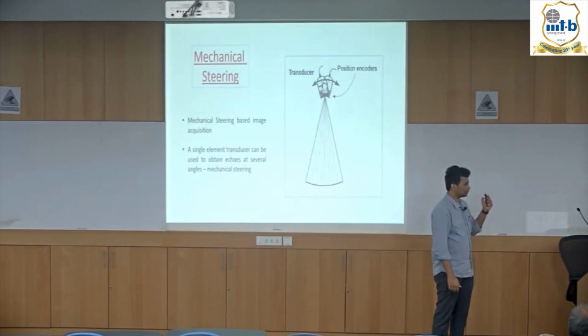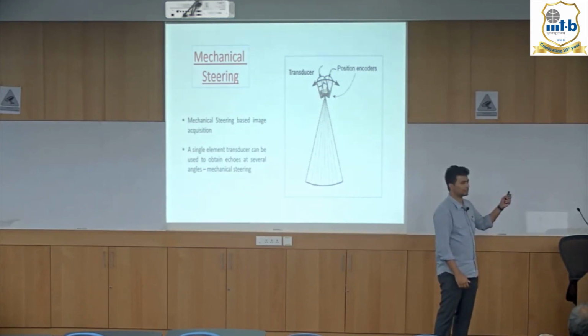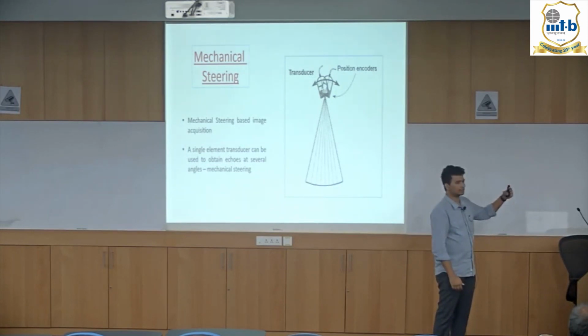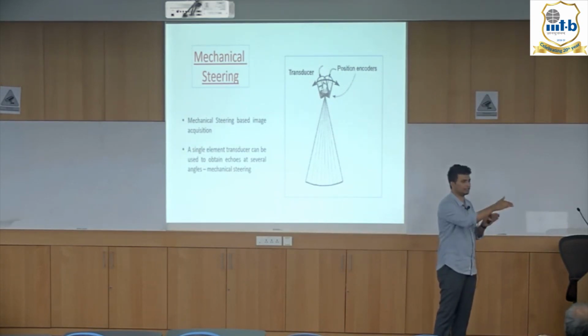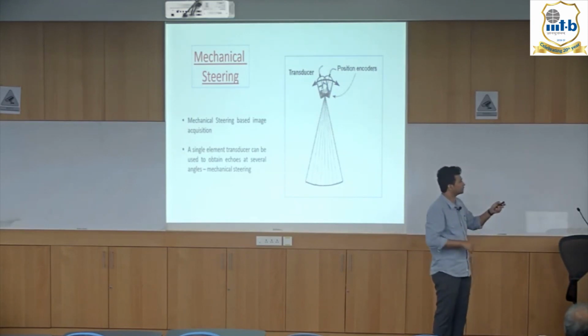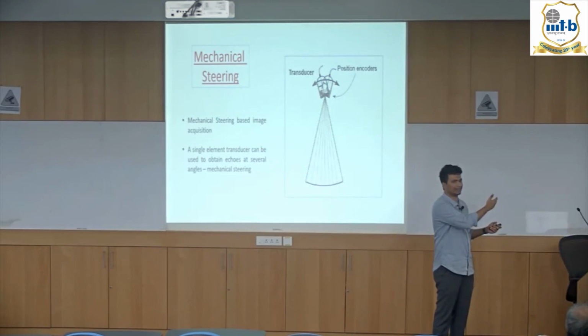Earlier people had tried to do the same thing using a single element transducer. What they had done was connect it to a motor and rotate the transducer at different angles, get echoes at all the angles, and make a sectorial kind of image. But this has limitations because it involves mechanical motion of the transducer, so the frame rate of the real-time video will be lower.